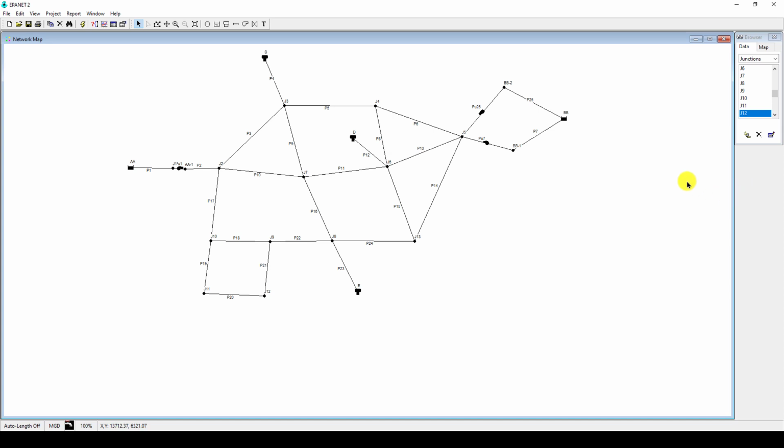So now the demands are set, and almost everything is sorted. The final thing that we need to design in our network is a pressure switch. Initially we have this low power pump 7 working when the simulation starts, but we want that when the head at node J13 goes below 240 feet at some time in the day, then P7 switches off and pump 25 switches on.